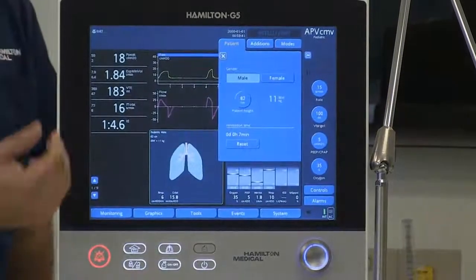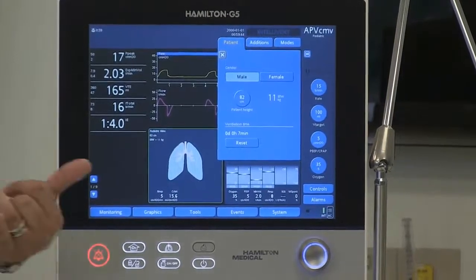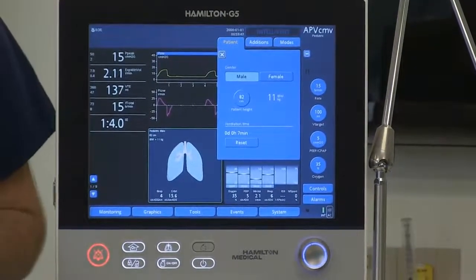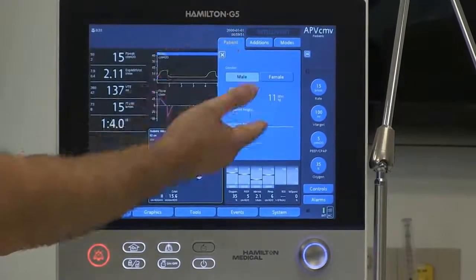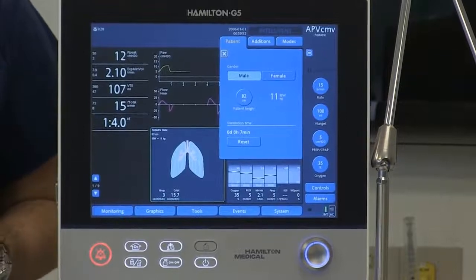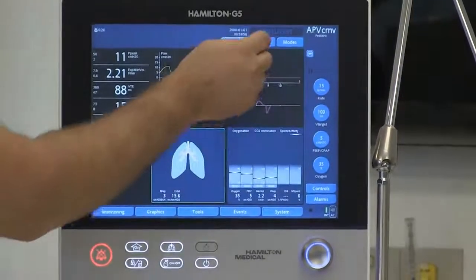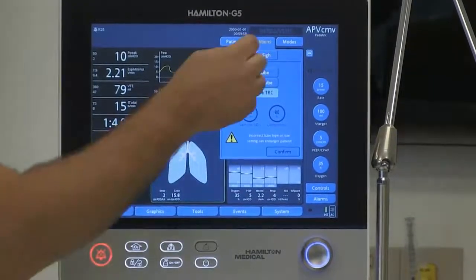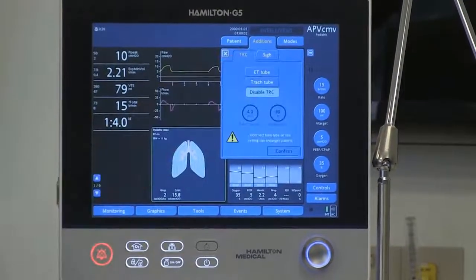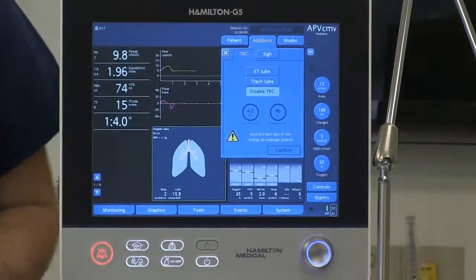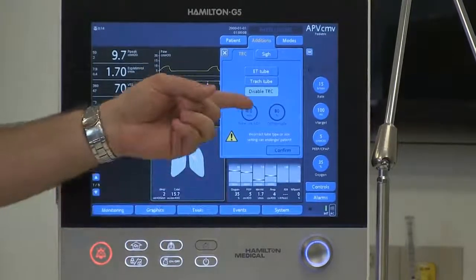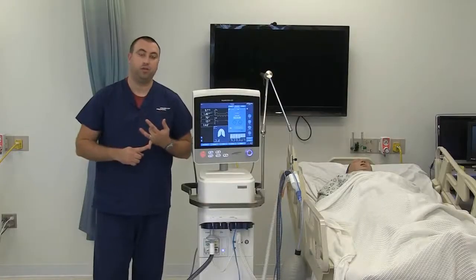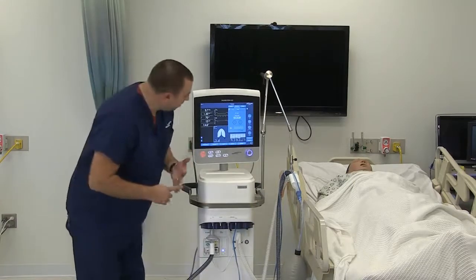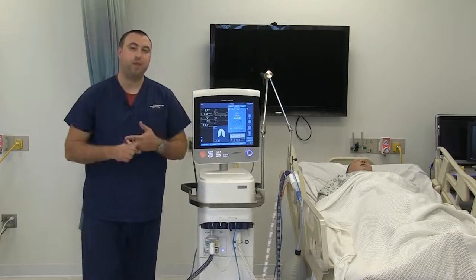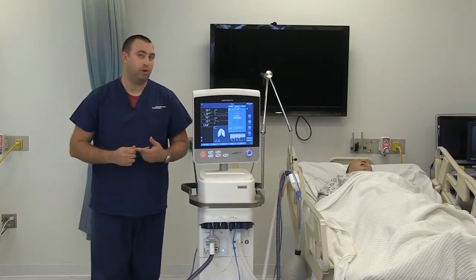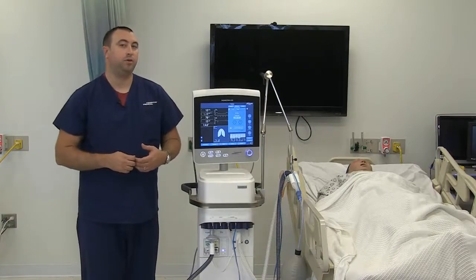In the patient section, if you did not have a chance to put in your ideal body weight, or if you had the wrong patient data, you can always go into the patient section and fix your height or gender and put that in accurately. Additions is where you'll find the option to do sigh breaths or tube resistance compensation. What this does is you would enter in the size of endotracheal tube or the size of airway you have, the level of compensation you want to give, and whether or not it's an endotracheal tube or a tracheostomy tube. And this will offer resistance support.